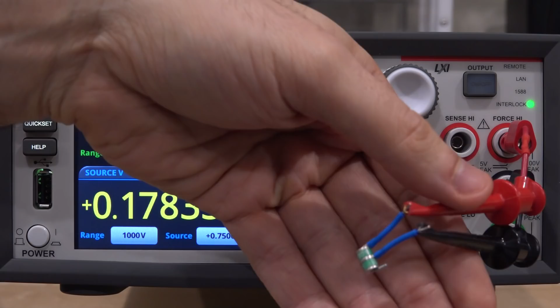So here's our next protection device. This is a gas discharge tube, and this operates entirely differently from how a varistor works. In fact, it's not even a solid state device at all. It consists of two electrodes separated by a certain gap, and inside the gap is trapped gas, which is allowed to ionize once the electric field across the two terminals exceeds a certain amount.